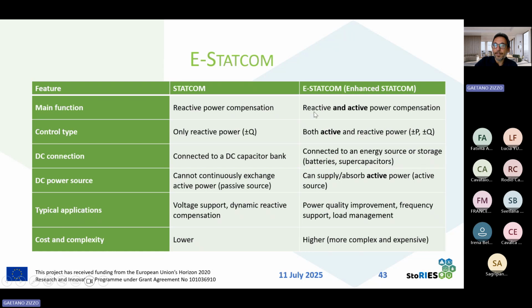It can regulate reactive and active power. The DC side is connected not only to a DC capacitor, but also to energy storage sources like batteries and supercapacitors. While the STATCOM cannot continuously exchange active power, and so it's considered like a passive source, the e-STATCOM can supply or absorb active power continuously. And so the applications are different. The STATCOM is used for voltage support and dynamic reactive compensation, while the e-STATCOM is used for power quality improvement, frequency support, and load management. Obviously, the complexity of an e-STATCOM is higher than that of the STATCOM.